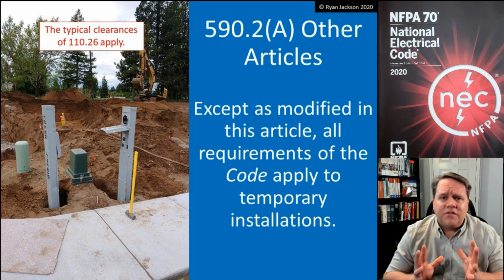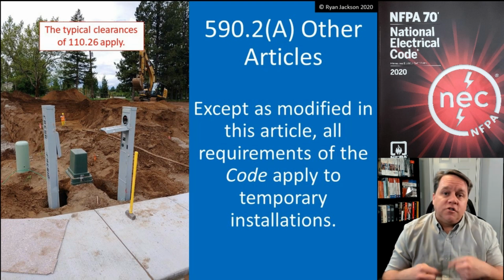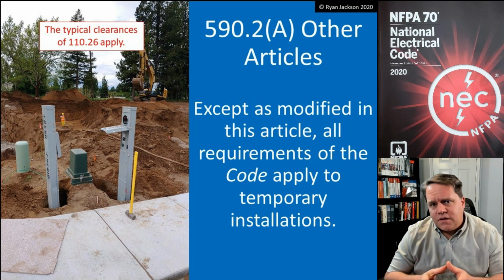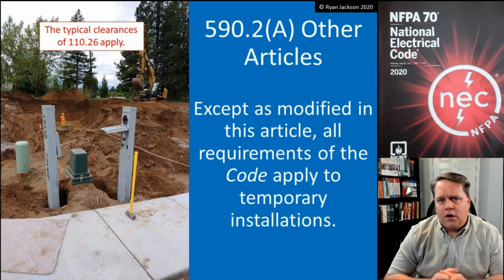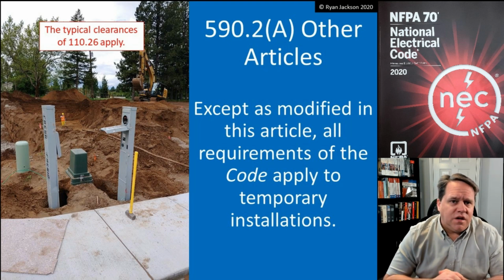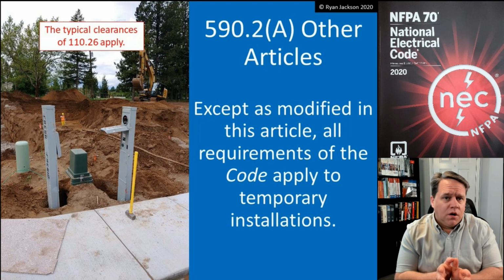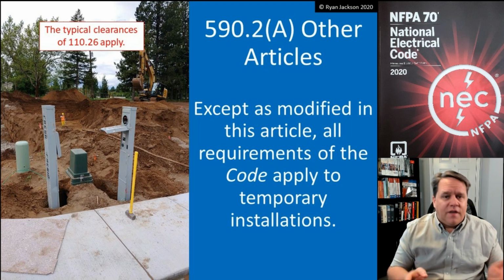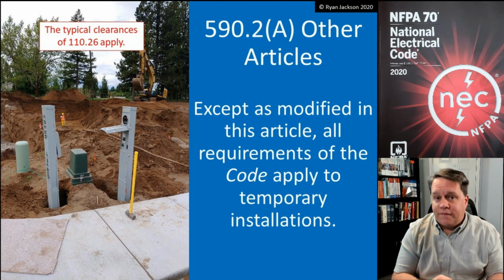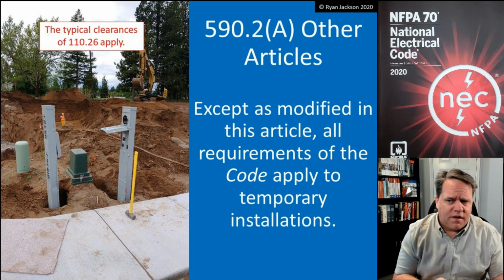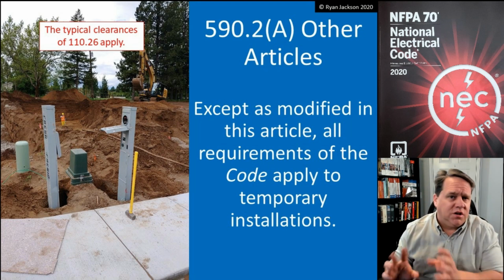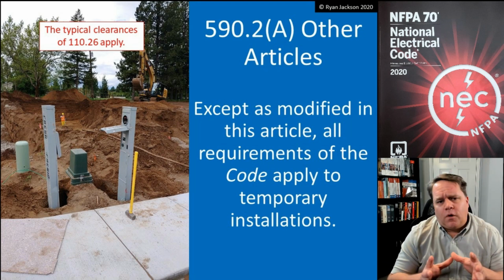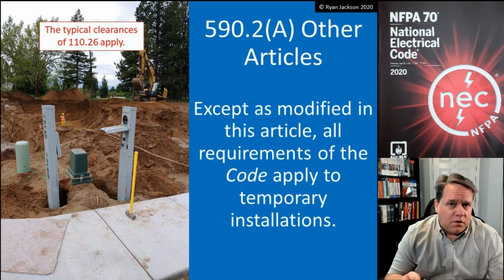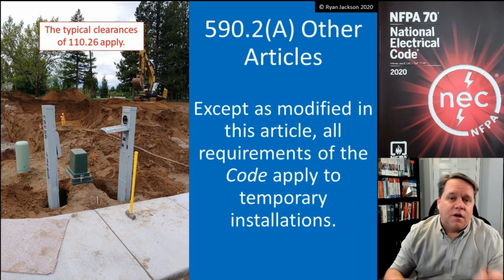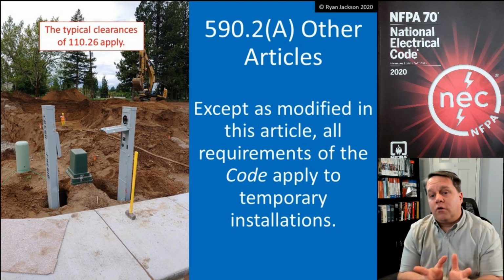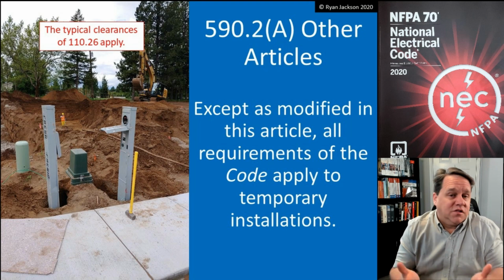590.2 is a very important section, and to be quite honest, even if it didn't say this, the code still gets you there. When you use 90.3 in the NEC, it says, look, chapters 1 through 4 apply to all installations. And then chapters 5, 6, and 7 supplement or modify the general rules in chapters 1 through 4. And then, of course, we have chapter 8, which is for communication, and that kind of stands on its own. But for power and lighting, chapters 1 through 4 apply regardless. And then chapter 5 supplements or modifies the requirements. So all the regular rules for a permanent installation still apply.